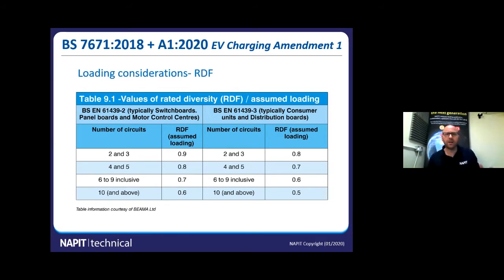This table is from table 9.1 from our on-site solutions publication. We've got a complete section on EV charging within that publication, so have a look at that if you've got time. Now, let's look at, say, a 10-way board. Most consumer units these days are at least 10 ways. If you see there, you've got a 0.5 factor. So what the manufacturers have done there is they are assuming that each MCB in that board, each circuit breaker in that board, is only working at 50% loading. Okay, that's the diversity that they've allowed for.